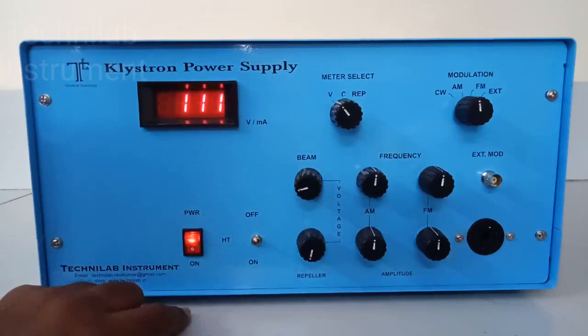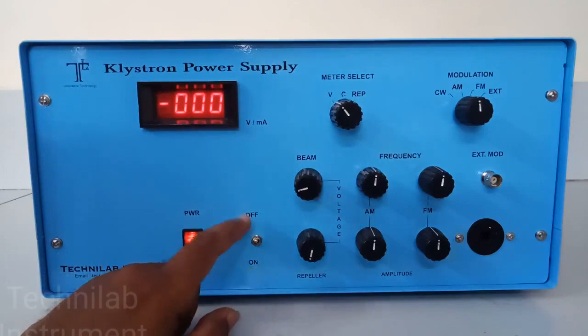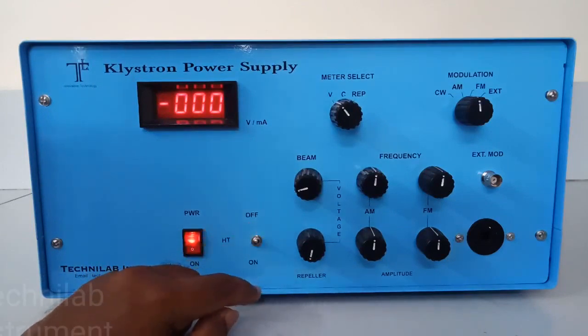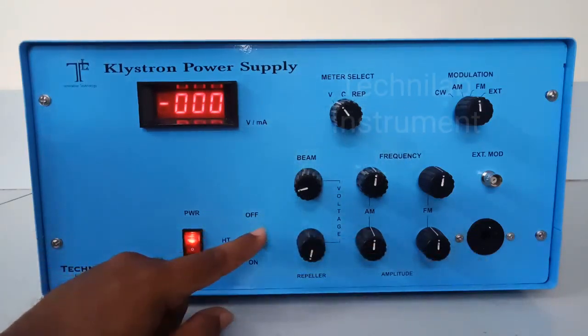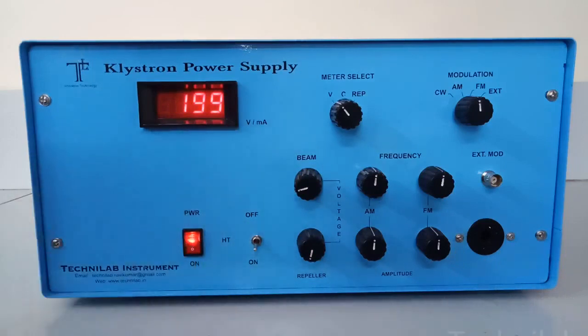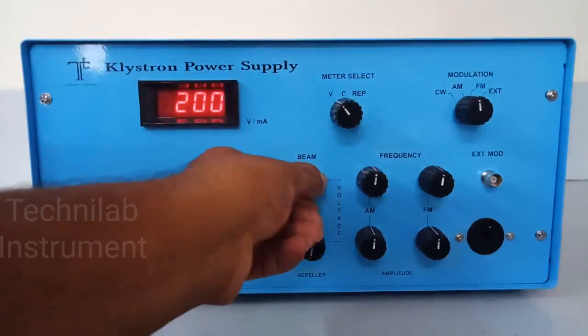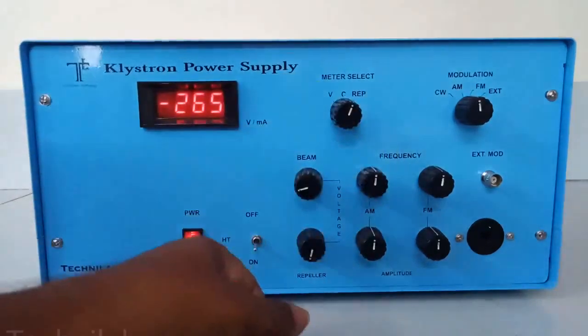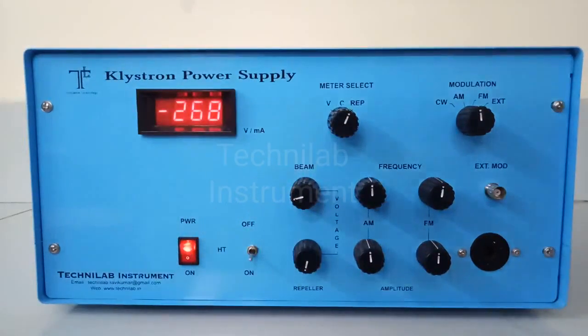Then you turn on the power supply. Now you can turn on the HT. When HT is ON, your beam supply and repeller supply are connected to your output; otherwise they will not connect to your circuit. So it is a safety feature. When I am conducting the experiment and taking readings, I will turn on this when I start my experiments. So it is now ON — I am getting beam supply. I can vary this beam supply. And this is the repeller.